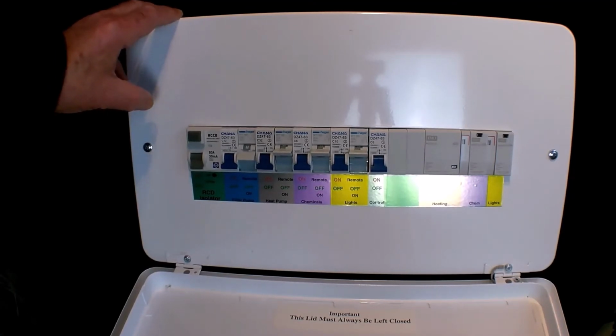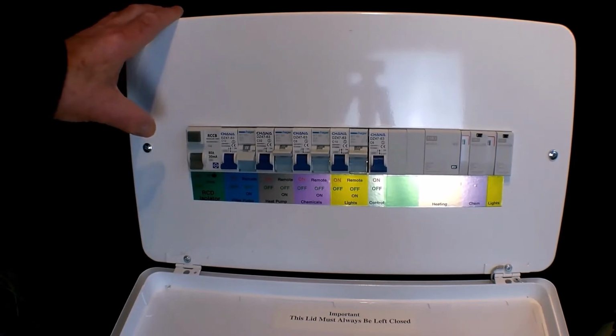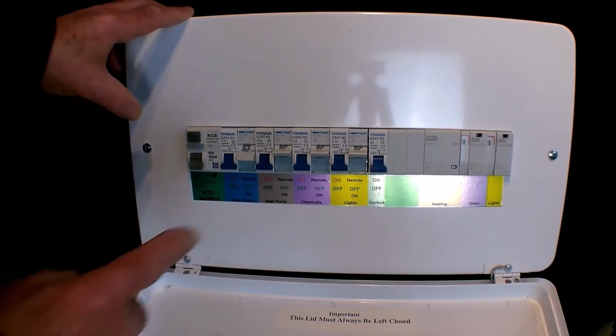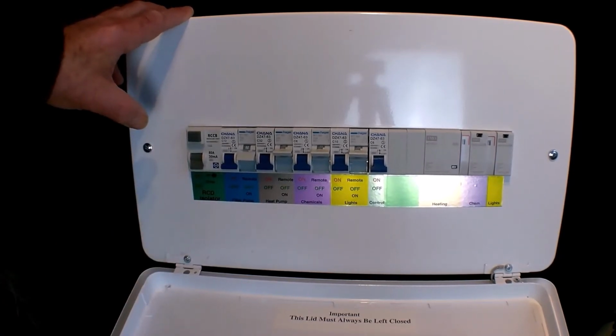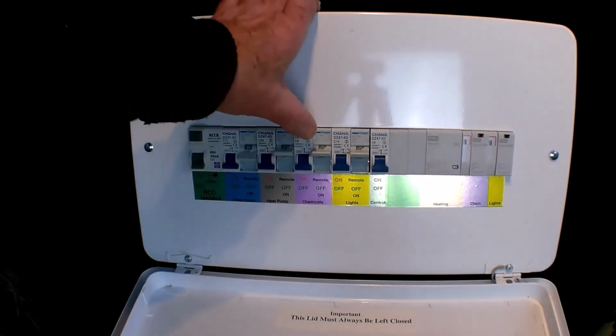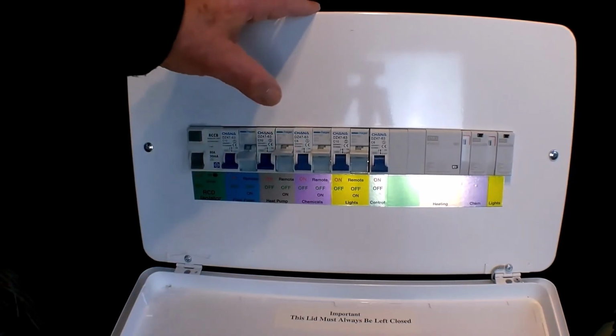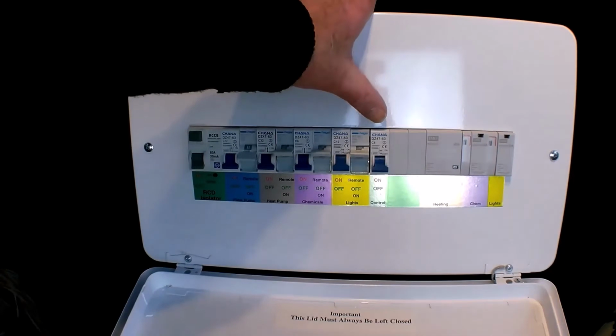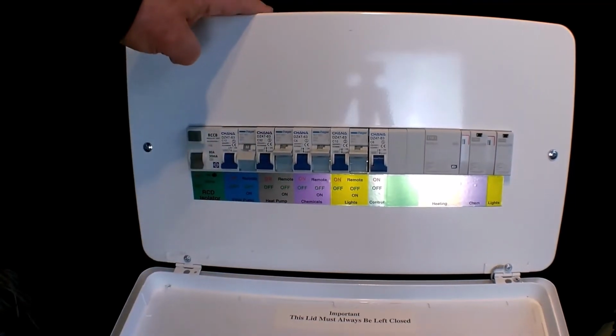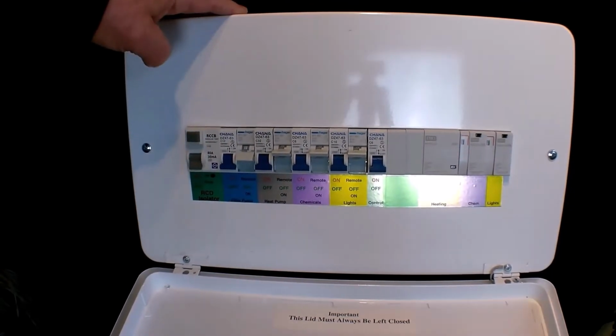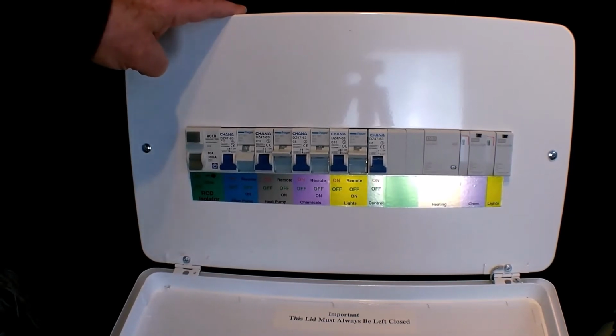If you want anything larger, then it will have to be in a deeper enclosure, but it can be assembled in anything you want it to be in. We've then got a heat pump circuit with local or remote control. We've got a chemical circuit and a lighting circuit and a last circuit is for feeding the BMS control device, because they must all be on the same circuit. Can't mix them up, otherwise you'll lose out on your interlocking when on remote.